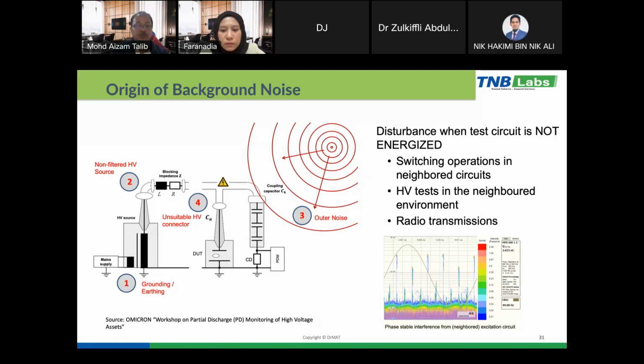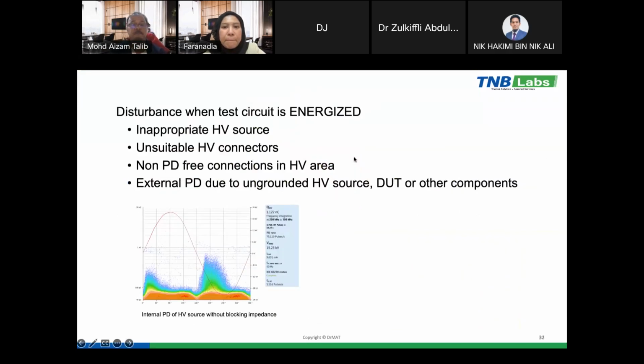And then when we use an unsuitable HV connector during the PD testing, it can also cause partial discharge. So overall, the disturbance when the circuit is not energized comes from switching operations in a neighboring circuit. Sometimes we need to do the test while the production lines are working. So this will disturb the PD measurements, and radio transmission can also interrupt the PD testing. Then when we energize, the disturbance comes from an inappropriate HV source, an unsuitable HV connector, a non PD-free connection in the HV area, and improper grounding of the measuring setup.